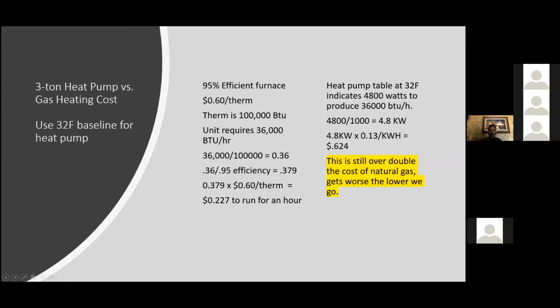So moving on a little more techie. When Refrigeration Ron first came to Airflow and we talked about using heat pumps and the cost of operating heat pumps and what's more efficient in COP, when we've presented VRF and heat pumps to folks, they're like, well, look, gas is so cheap, you can't possibly heat with electricity and be competitive. And so let's just do the math real quick. If you're looking at a furnace, for example, 95% efficient, and the cost is 60 cents a therm, which is 100,000 BTUs. And let me back up just a half a sec. We're talking about a 3-ton, so a 36,000 BTU unit.